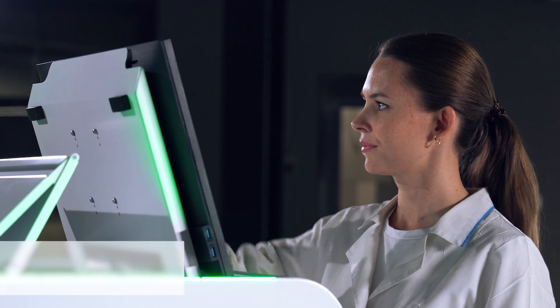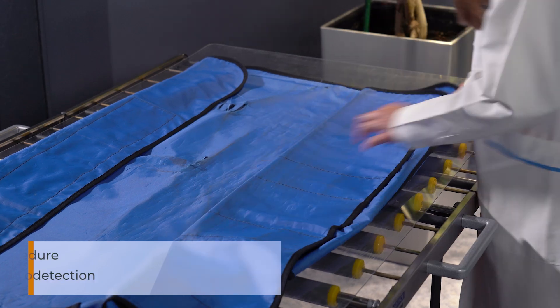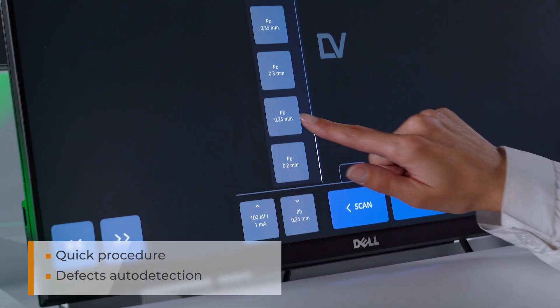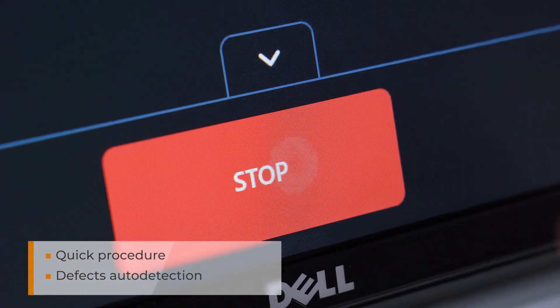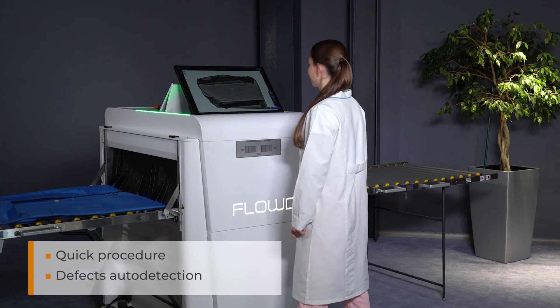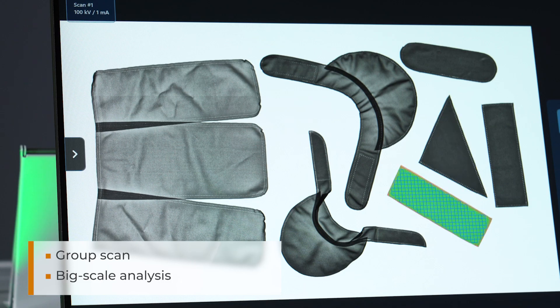The device has a self-intuitive and user-friendly interface. It is easy to operate. To analyze an item, we place it on a substrate, select an X-ray mode, lead-equivalent, and start scanning — and in just 15 seconds, the analyzed item appears on the screen. Several items can be inspected in one scan to save time.